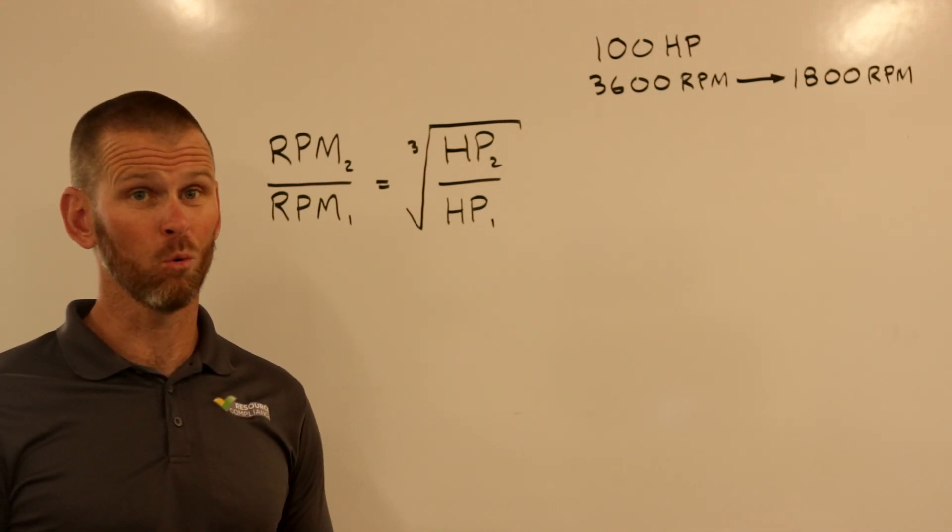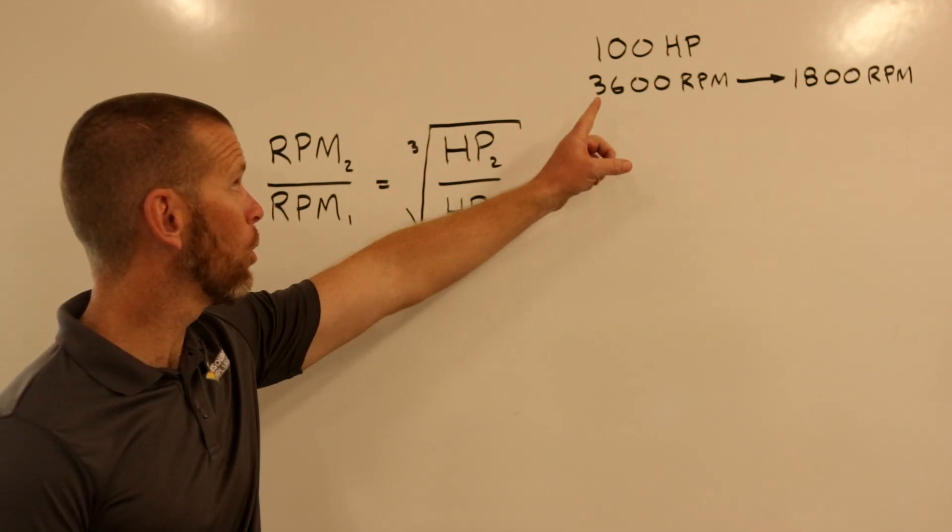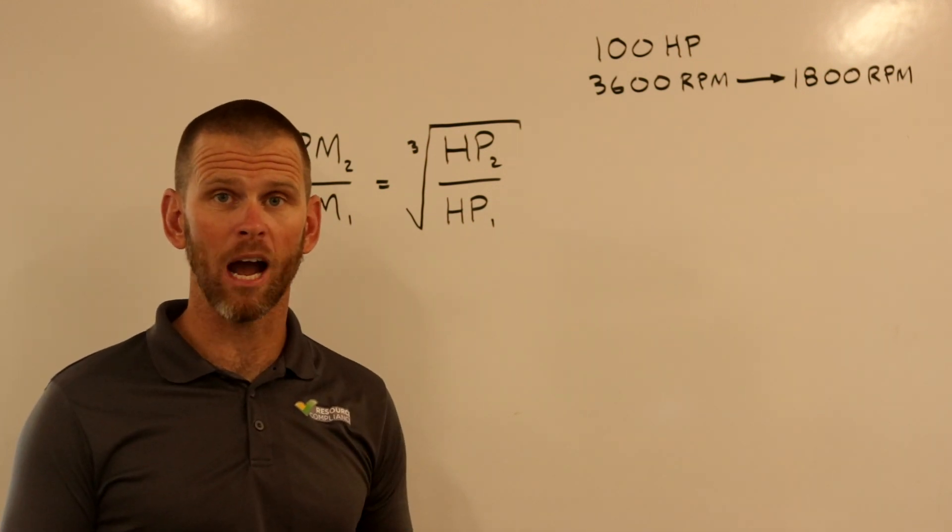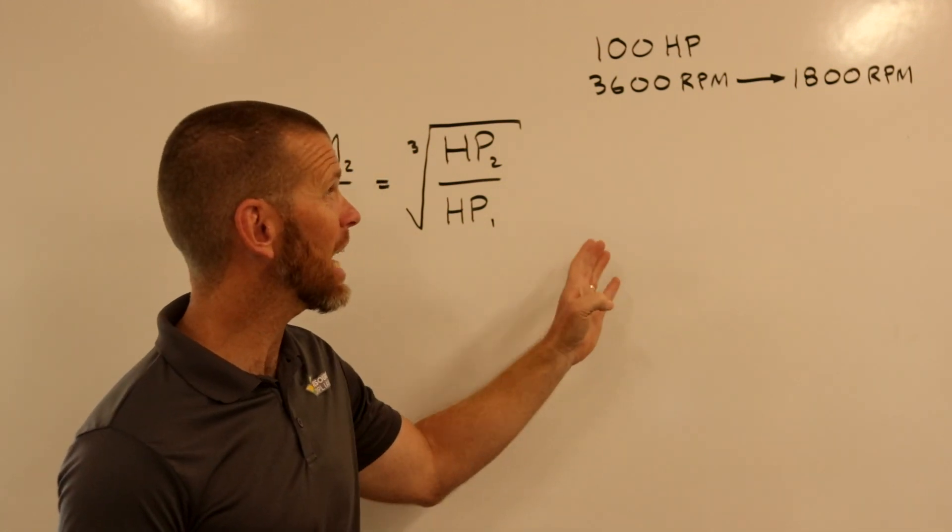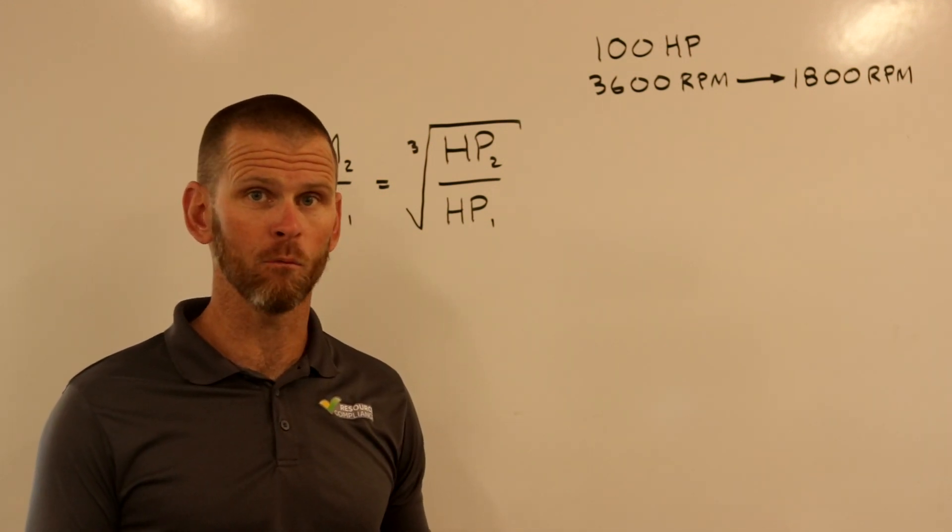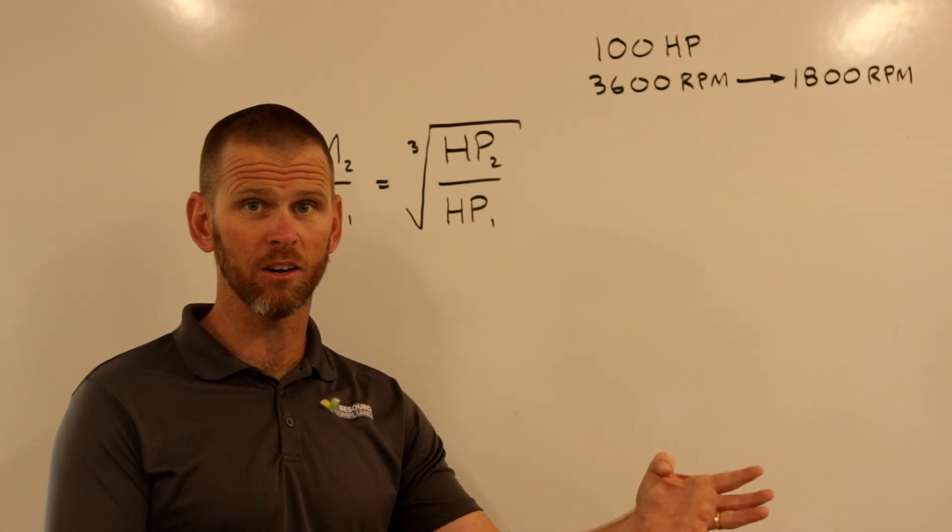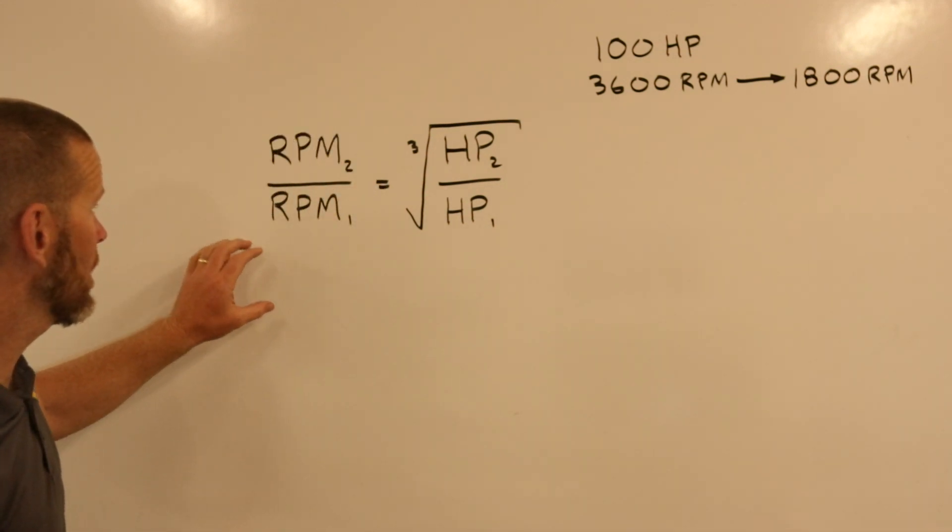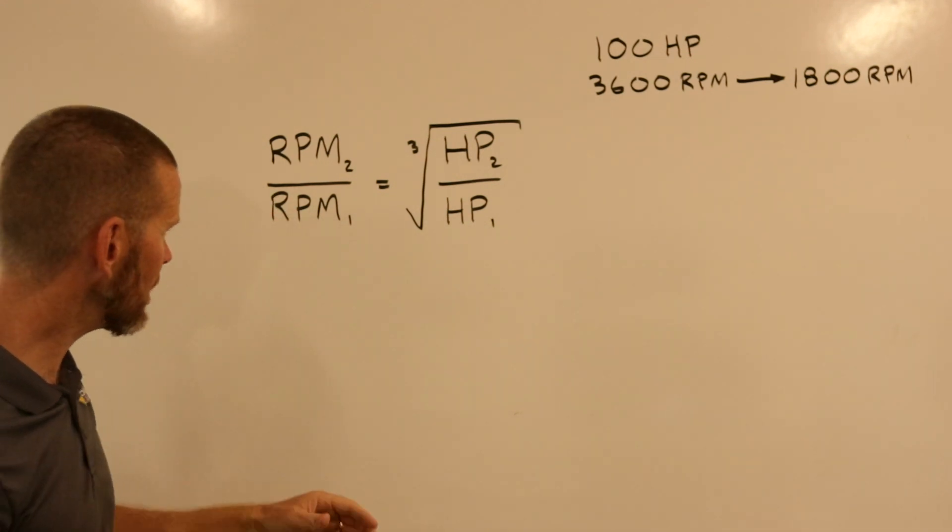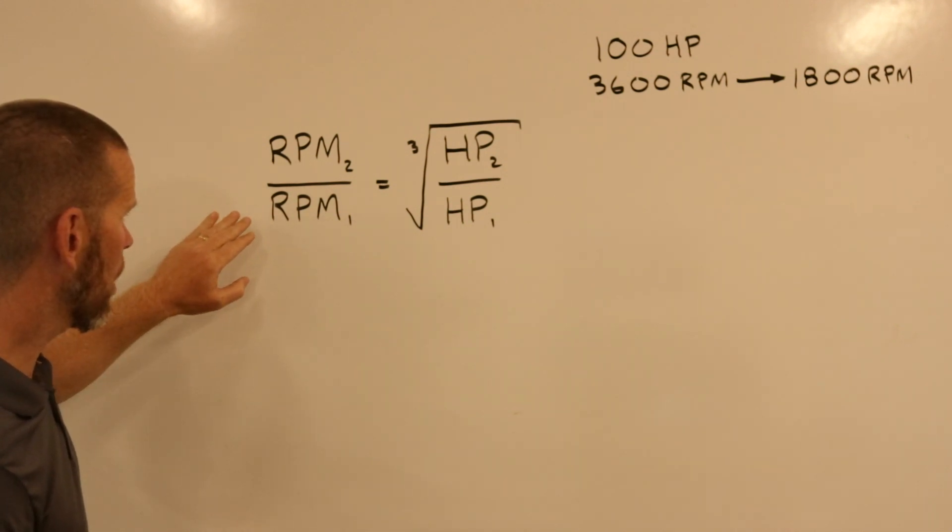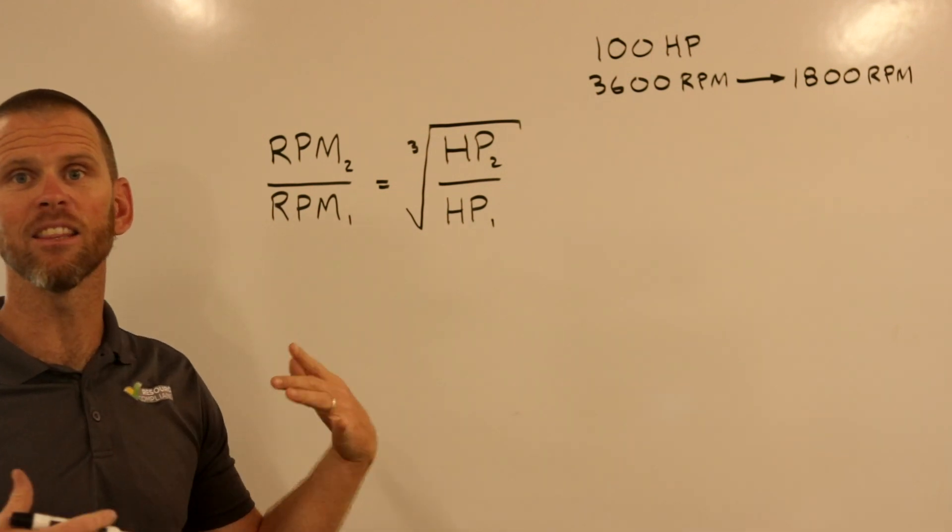So in this example, I want to show what the power savings or energy savings are when you lower the speed of a compressor motor or really any motor. This would apply to any motor, but in our application of refrigeration, we're talking about unloading compressors. So let's say we have a 100 horsepower compressor and we use a variable frequency drive or VFD to lower the speed of the motor from 3600 RPM, which is its natural or max speed, down to 1800 RPM, which is exactly 50%. We're going at half speed. The variable frequency drive would do this by reducing the frequency of the power from 60 hertz down to 30 hertz. We already learned that the relationship between RPM and horsepower is a cubic relationship.